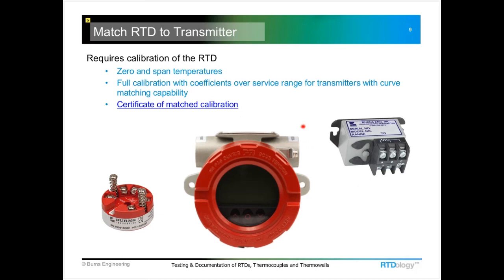Some of the transmitters don't have the interpolation equations in their software. You can also use this calibration information to set just a simple zero and span. This transmitter, for example, is analog, and it has these little potentiometers in it where you can adjust it to a given milliamp output with known resistance input from the temperature probe.